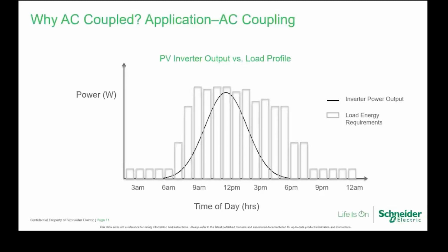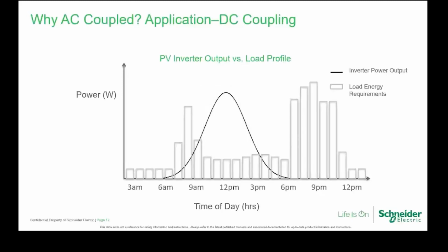However, if your battery loads are in the evening or early morning, you're better off with a DC coupled solution, as then you can store the energy being generated during the day, and that can then be used at nighttime or in the early mornings. So I said to you, you've got to make sure you do the load profile first to see which one will be more suitable.